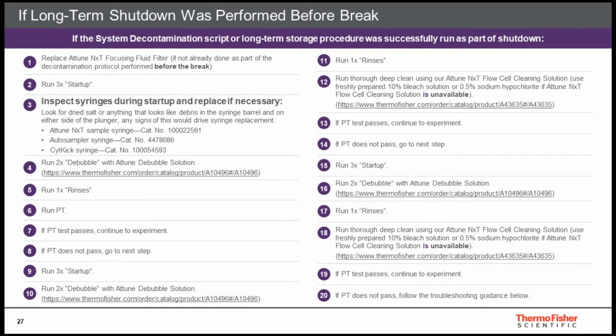Now let's talk about the second scenario, where the instrument was stored properly before shutdown, either by running the system decontamination script or a long-term shutdown procedure where the Attune NxT was rinsed with ultra-pure water and then left dry. When restarting the system from this state, please start by ensuring that new focusing fluid filters are installed on the Attune NxT, because keeping old focusing fluid filters after system decontamination can be detrimental to the system. Next, follow the 3-2-1 rule to run 3 startups, followed by 2 debubbles and 1 rinse.